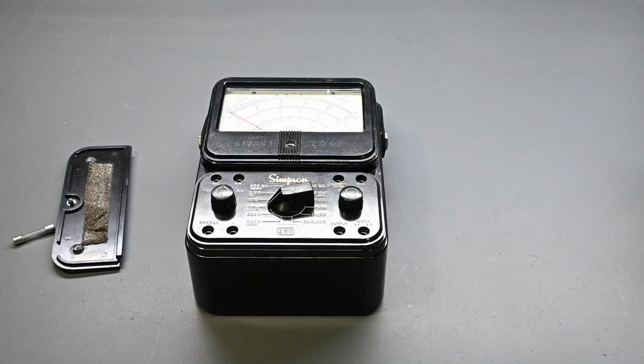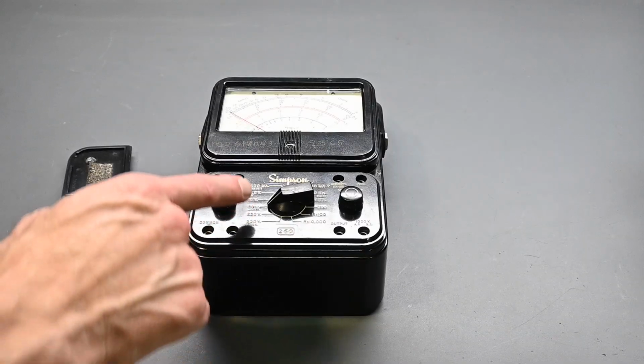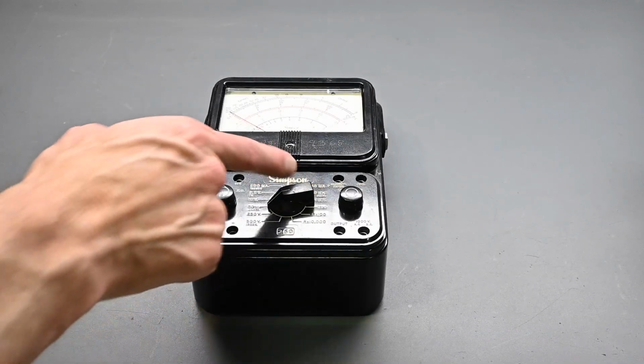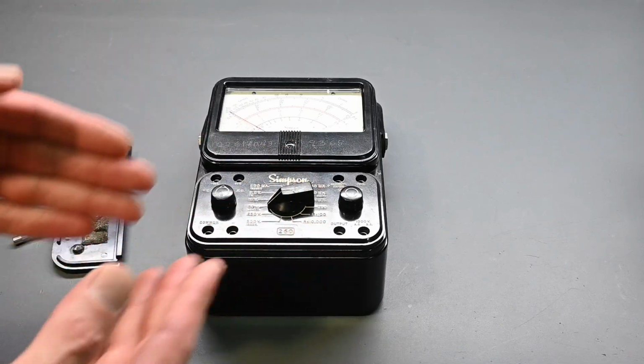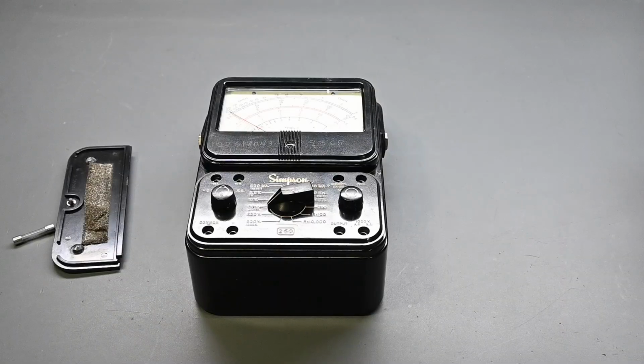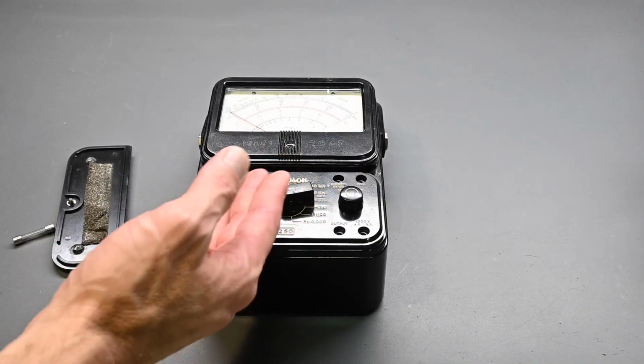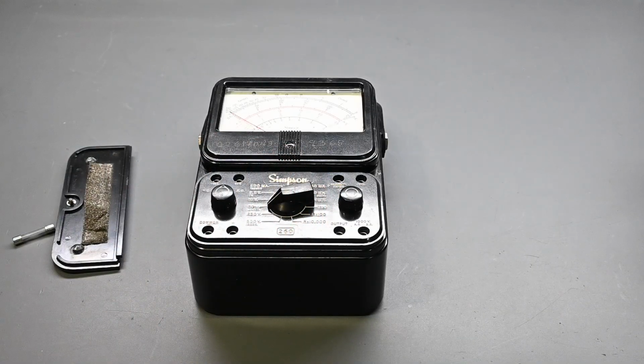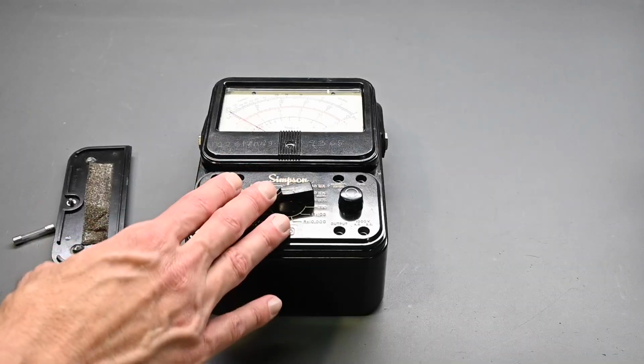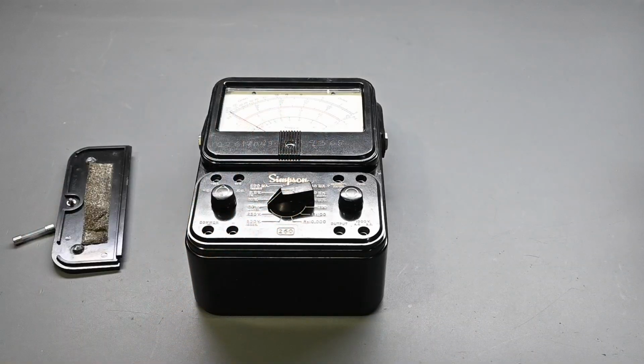A common reason the fuse blows is that, say, the meter's in the current measuring ranges, 500 milliamps or 100 milliamps and so forth, and then you take the test probes and measure AC line voltage, or across a battery, or a power supply. That takes the fuse out for protection because the meter has a very low impedance at that point. If a 15 amp fuse was in there instead, something else would go up in smoke, because the switching, wires, resistors and so on would easily be damaged, while the 15 amp fuse would just sit there. That 15 amp fuse got put in place because the fuse prior to it would have been damaged, maybe from an overload condition.